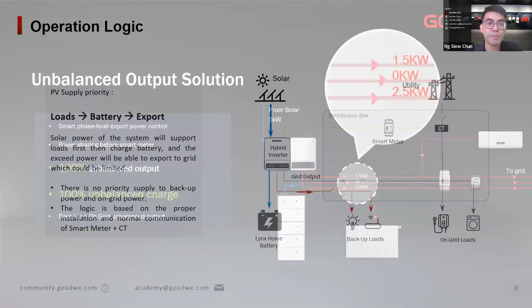In terms of PV supply priority, by default the PV solar power will be delivered to the backup load as well as the on-grid load. Our highest priority is for solar power to be delivered to the loads. Next, when there is still excess power, we will charge the battery. Only when the battery is already fully charged will we consider exporting power to the grid. That is the default logic of our inverter.